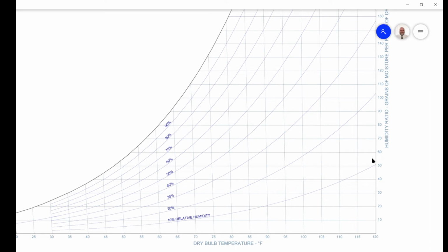If we take that as our state point, what we immediately notice is that it is between the two lines of 50, sorry, that was a bad drawing, 50 and 40%. It is closer to 50, so I would say maybe it is 46 or 47% relative humidity. So relative humidity is 46 or 47 percent in this case.